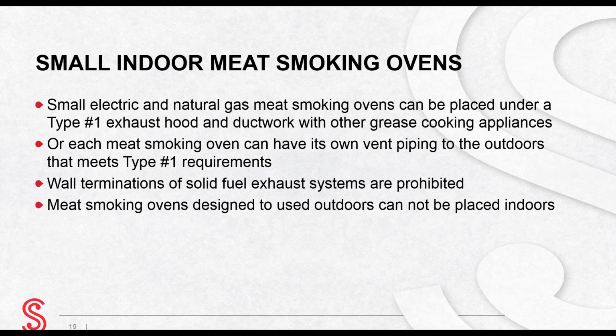Small electric and natural gas meat smoking ovens can be placed under an NFPA 96 Type 1 exhaust hood and ductwork or other grease cooking appliances. NFPA 96 Type 1 exhaust hoods and ductwork is what you see in commercial kitchens that do grease cooking using griddles, broilers, and fryers.